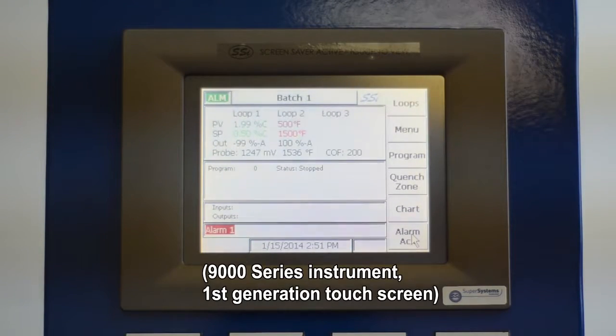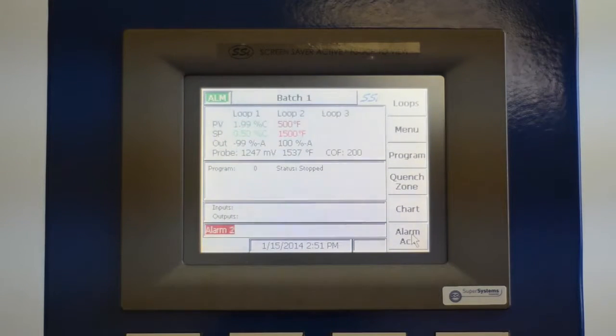Once finished with the zero and span calibration on input 3, you're going to remove your copper wire from terminals 27 and 28 and put your TC wire on, and then source a temperature from your sourcing meter. In this case I'm sourcing 500 degrees, and I'm going to check the span of the entire range, so I'll take it up to 1,000 degrees for my sourcing meter.